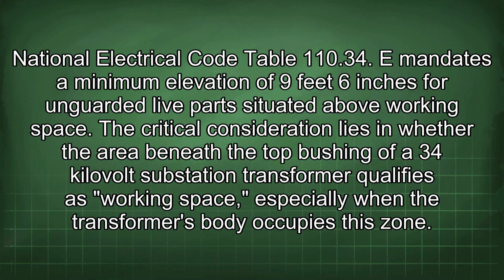National Electrical Code Table 110.34(E) mandates a minimum elevation of 9 feet 6 inches for unguarded live parts situated above working space. The critical consideration lies in whether the area beneath the top bushing of a 34 kV substation transformer qualifies as working space, especially when the transformer's body occupies this zone.